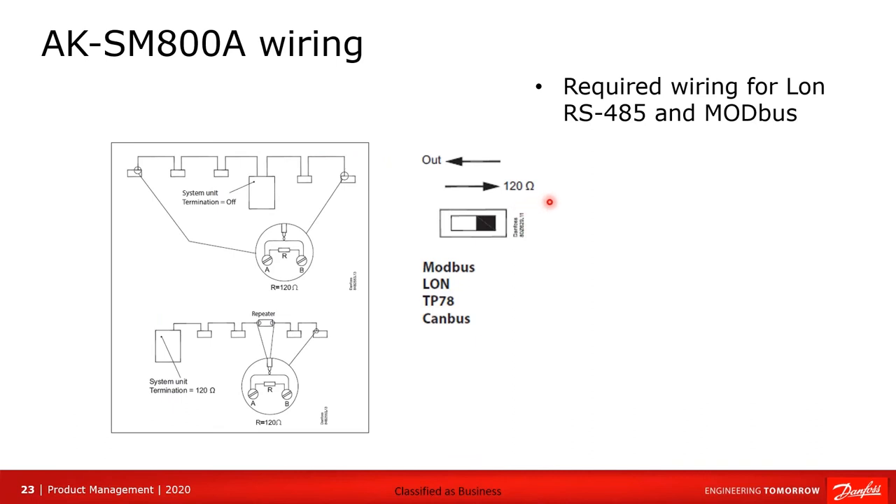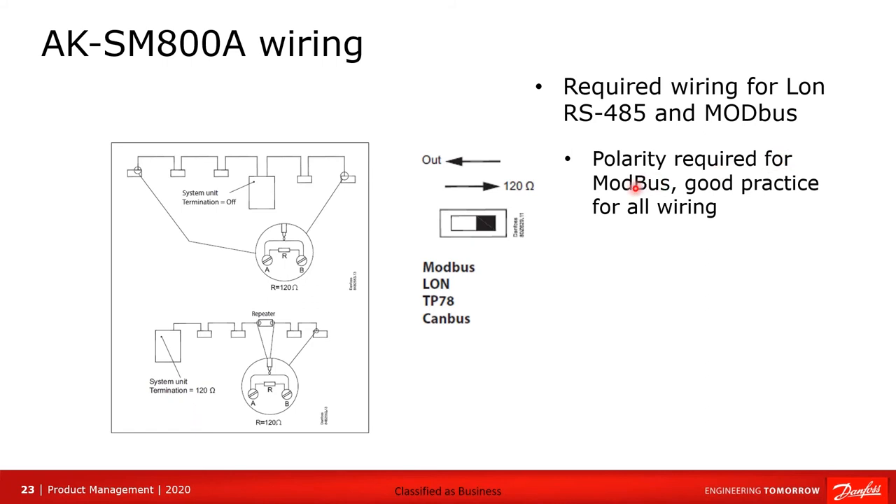Wiring is a very important piece. To have a robust network, we must follow specific rules. Required wiring applies to Lon RS-485 and MOD bus. Polarity is required for MOD bus. Lon doesn't technically require polarity, but following it is good practice. Connections must be daisy-chained point to point — that is the only acceptable topology for Lon or MOD bus networks.